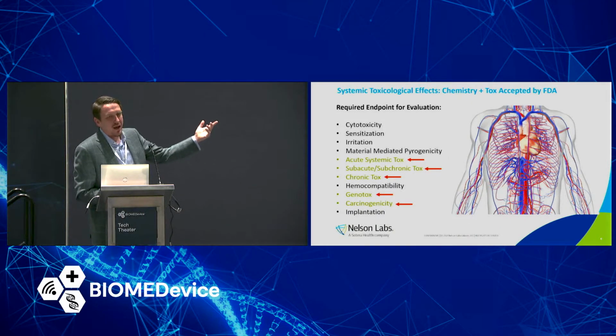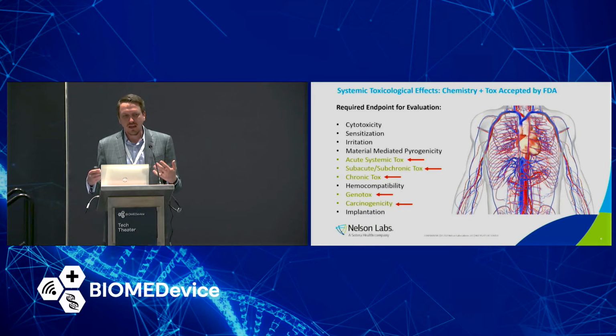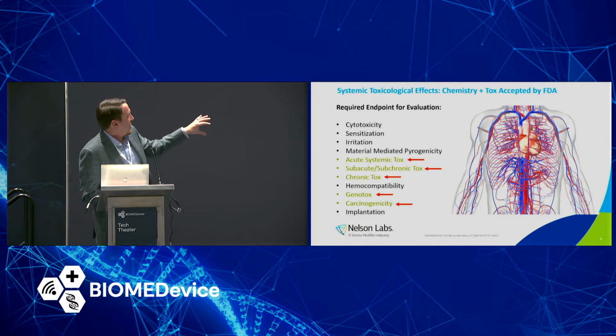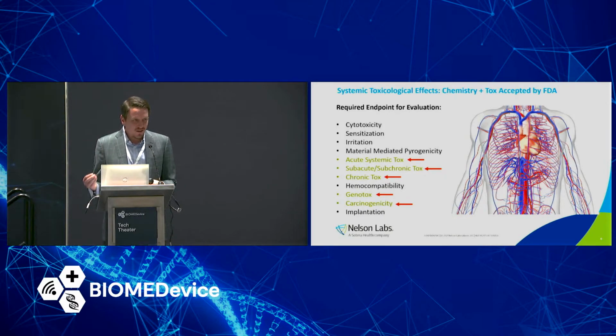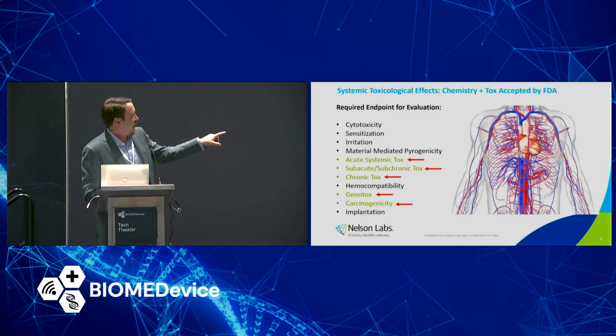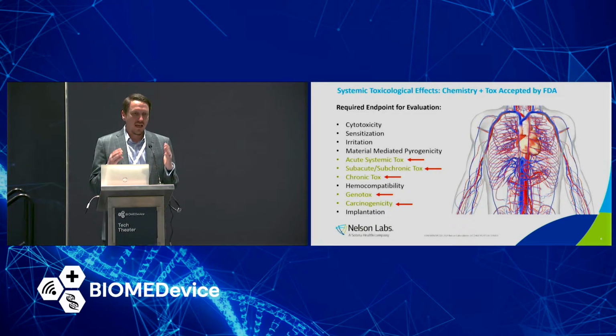I also put hemocompatibility on there. That's in case it's in contact with circulating blood, direct or indirect. And of those risks, some are specifically systemic toxicities. When I say systemic toxicity, this means related to compounds that are dissolvable in the body that can get distributed throughout the entire body, either by the vascular system or the lymphatic system. So all of those in green with the arrows, those are the types of risks related to being distributed through the body. And the FDA has explicitly said, for the ones with the arrows, that they will take extractables testing and a toxicological risk assessment as a means of addressing those biological risks.